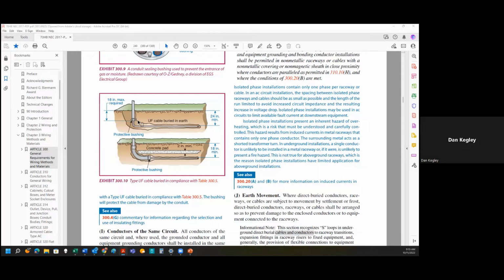It needs a seal. A lot of times, when I'm doing installations, I'll use a product called Duct Seal. It's a putty kind of material, a grayish putty looking material. It's used in a lot of HVAC duct work. That's why they call it Duct Seal. And it's basically a nice little clay putty type material that you just pack around the conductors at the top of the box as it comes into that junction box.